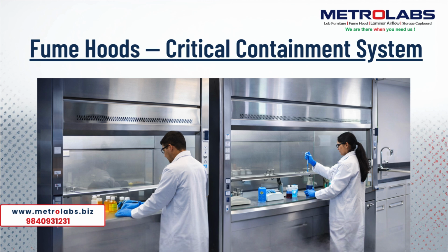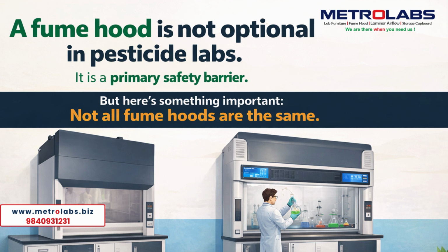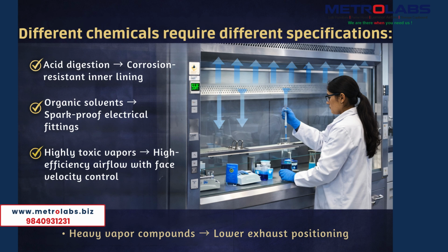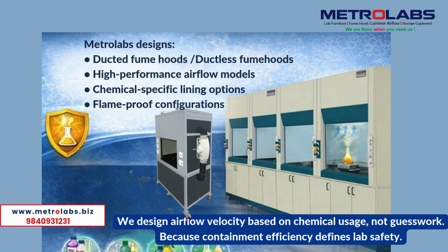Fumehoods, critical containment system. A fumehood is not optional in pesticide labs. It is a primary safety barrier. But here is something important. Not all fumehoods are the same. Different chemicals require different specifications. Acid digestion leads to corrosion-resistant inner lining. Organic solvents leads to spark-proof electrical fittings. Highly toxic vapors leads to high-efficiency airflow with face velocity control. Heavy vapor compounds leads to lower exhaust positioning. Metrolabs designs ducted fumehoods, ductless fumehoods, high-performance airflow models, chemical-specific lining options, flame-proof configurations. We design airflow velocity based on chemical usage, not guesswork. Because containment efficiency defines lab safety.